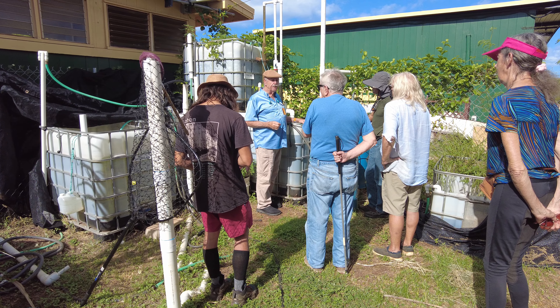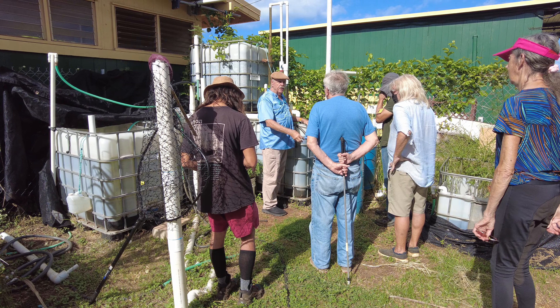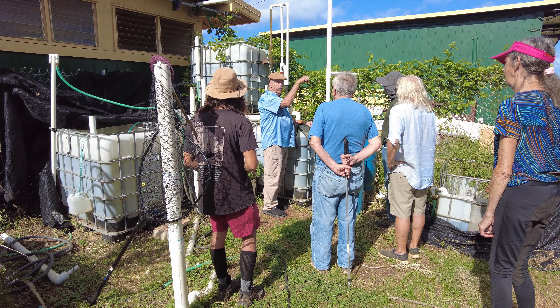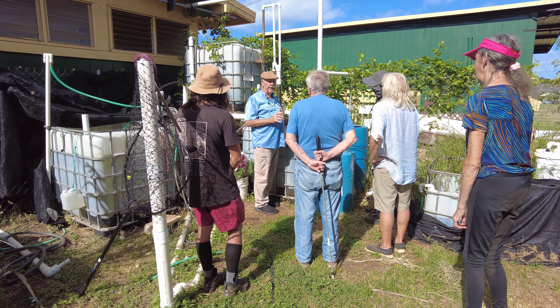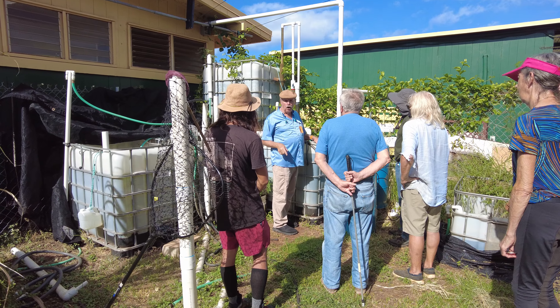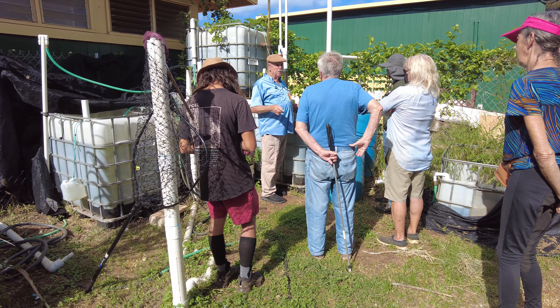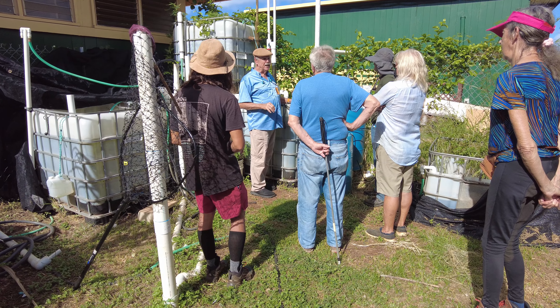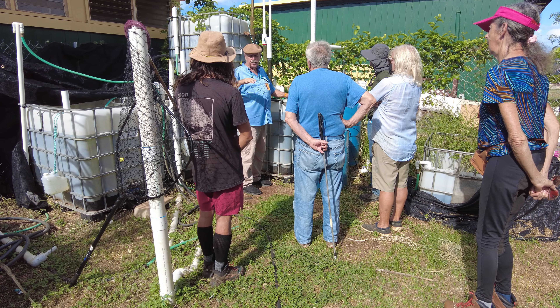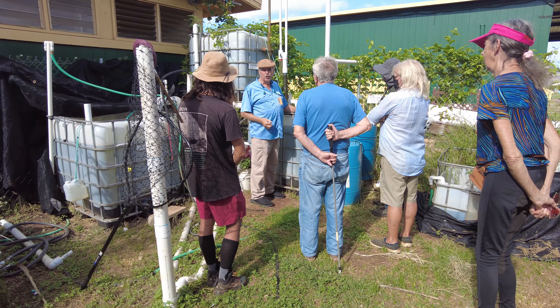He said, how many 90s do you have? All these water pumps come with the outlet coming straight up, then I make a 90, then I go to the ground, then I make a 90, and then you put a check valve, and then it goes off 200 feet. When it gets to the fish tank, there's a 90 going up, going over, and going up. He said, so that's six of them. Let's look at the resistance of fittings — two-inch 90s at a foot and a half each, so you have nine feet of resistance. Nine and 12 — this is not sounding good. Now let's look at your pump. Your pump's maximum head is 26 feet, but at five feet you get 2,000 gallons per hour; at 10 feet you get about 1,500 gallons per hour. The higher you go, the less you get. And he said, wow — you're getting 1,000; the chart shows you should only be getting about 700. So you're doing pretty good.